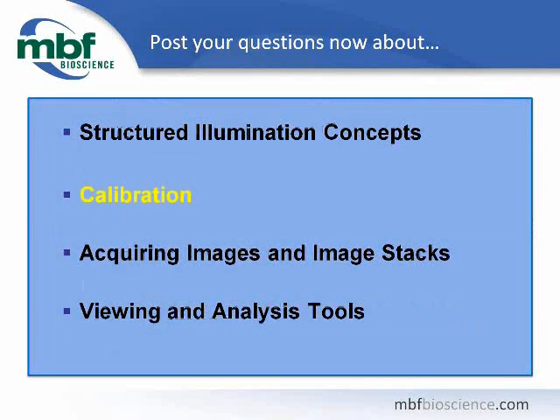We're going to pause to answer questions. We've been asked how stable the calibration is from session to session. The calibration should last quite some time — weeks, if not months. You will notice when your calibration is insufficient because residual grid lines may start appearing in your images. If that is the case, you'll want to redo the phase calibration.